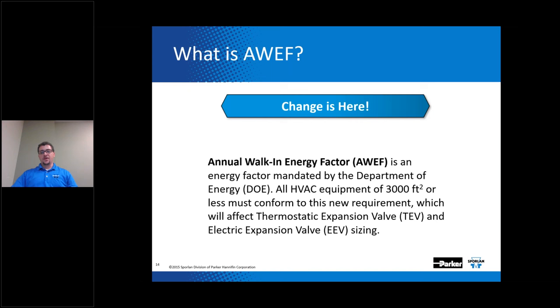If your walk-in cooler or freezer is 3,000 square feet or less, condensing units and evaporators manufactured after July 2020 have to conform to the AWEF standard. In order to meet the energy factors, OEMs have actually lowered their head pressure settings on their equipment, thus allowing them to lower the compression ratio and save energy at the compressor.